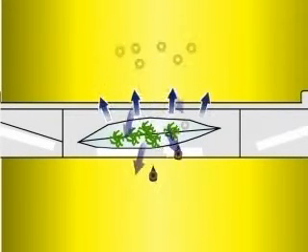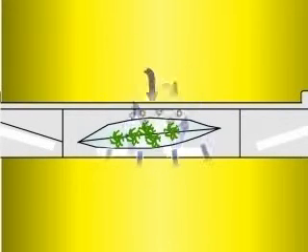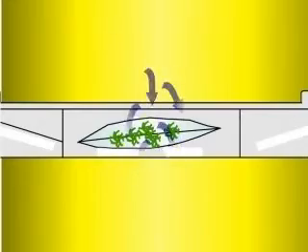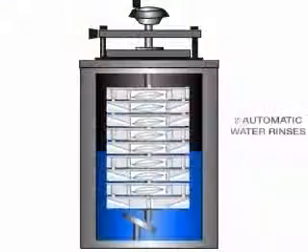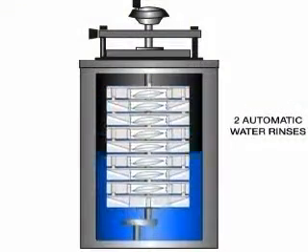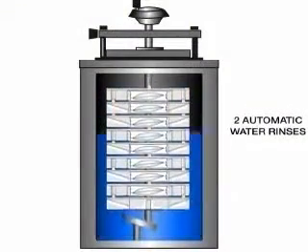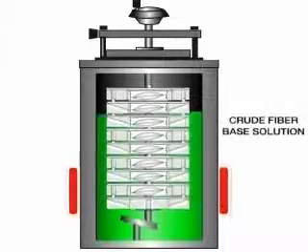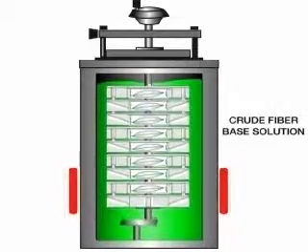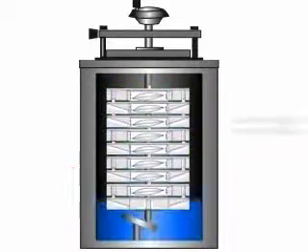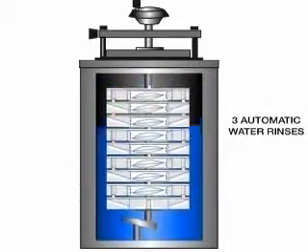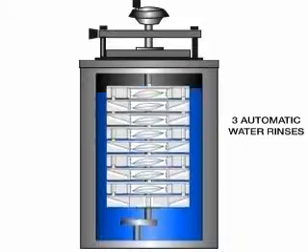During a crude fiber analysis, the A2000 automatically follows the acid step with a series of hot water rinses before moving to the base step. A final series of hot water rinses are automatically performed, completing the process.